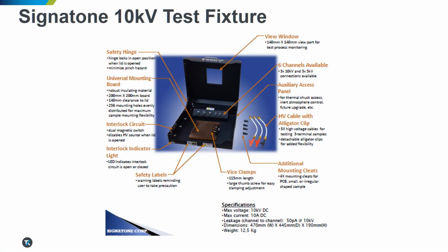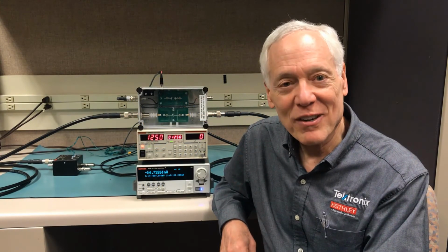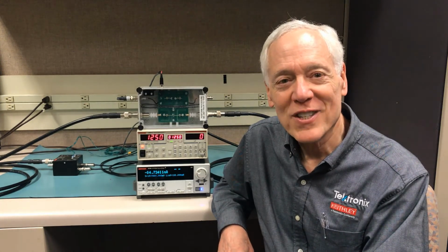I want to make you aware of a nice safety test fixture rated for 10 kilovolts made by Signatone. The test fixture uses a universal mounting board to accommodate a wide range of devices under test. High voltage connectors on the test fixture are compatible with the Keithley 5 kilovolt and 10 kilovolt high voltage power supplies. Thank you for letting me show you how to accurately and safely perform high voltage testing.